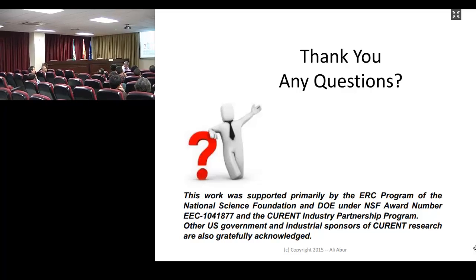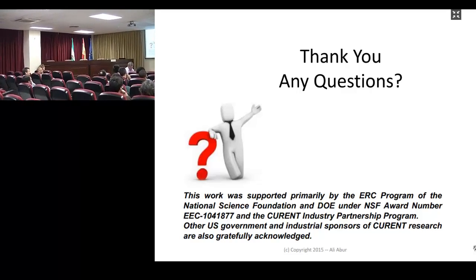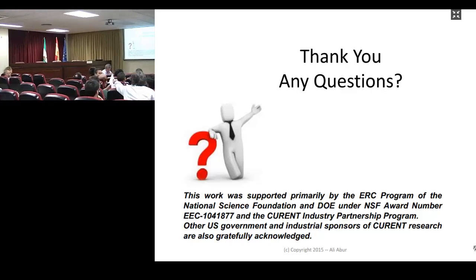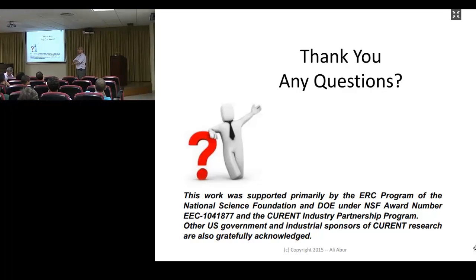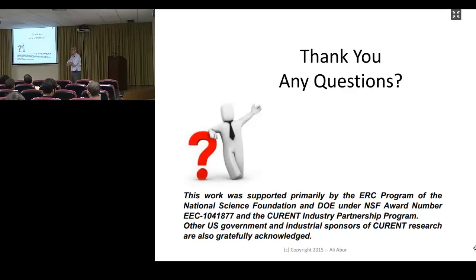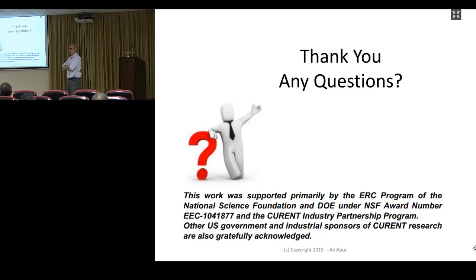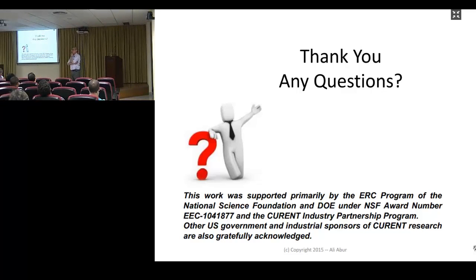Yeah, I don't want to put a value because I asked the same question to the manufacturers and different utilities, and they give different answers, going from $1,000 to $10,000. But I think the reason it's not a direct answer is that the box itself is not expensive. I think the infrastructure, like any fiber connection or antennas or the communication setup in the substation, so whether the substation is ready for this sort of installation or not, makes the cost different. So the same PMU may cost different amounts to different utilities depending on how their substation is right now. So that's my understanding. But the actual cost changes.